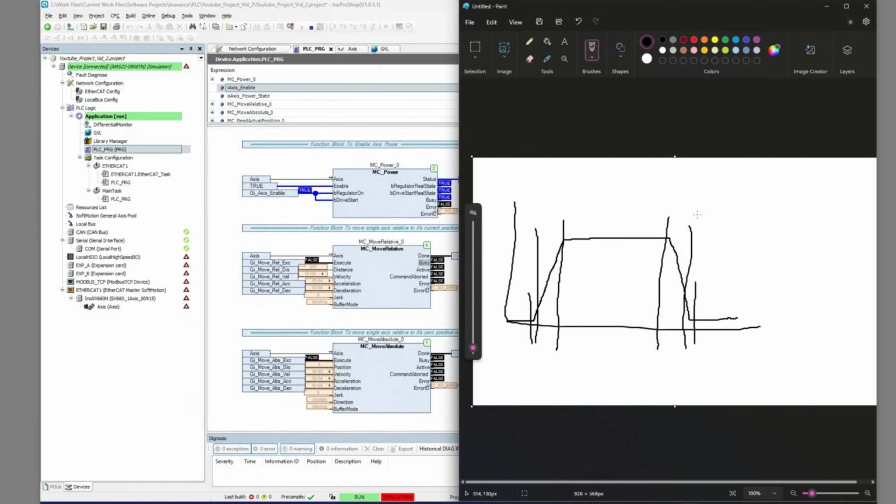So an example of this is if my velocity is, let's say, 10,000 and my acceleration and deceleration are only set to 10, what will happen is that our velocity set point, which is all the way up here, because our acceleration and deceleration are too low, the actual profile that we'll end up getting will look something like this, where we've just got a triangle rather than meeting our nominal speed in a trapezoid.